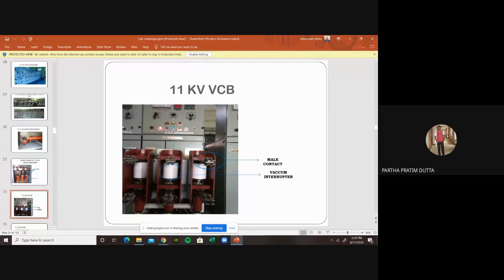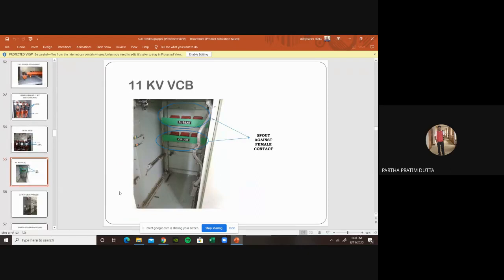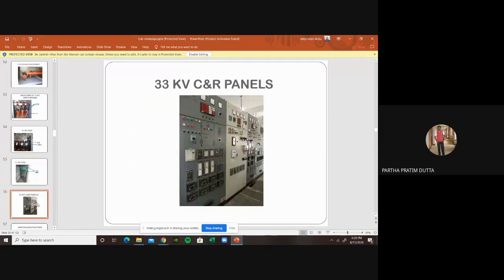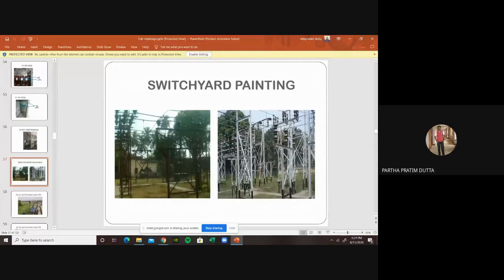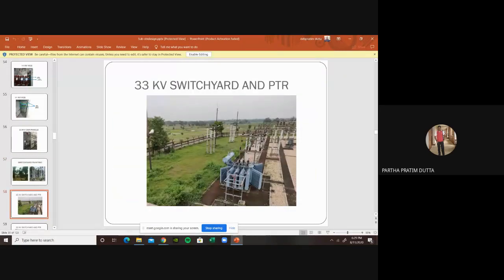And these are the male contacts. These are the chambers where the entire make-break system is placed. This is basically the spout, and this is the 33 kV control panel. All the controls, CT, VCB, are done over here. And this is the switchyard painting we usually do to restrict erosion and so on. This is the structure where the bus bar is, the pipe bus bar you see, and these are the insulating supports as well as the isolator, and the VCB is in place. These are the switchyard PTR.